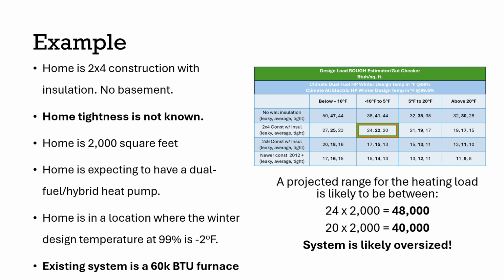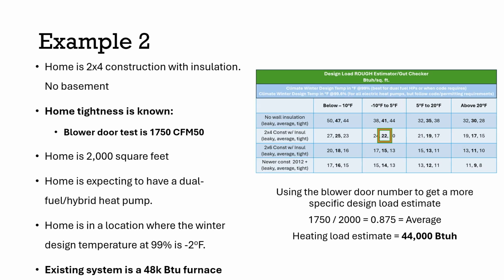So if I'm that technician out on that no heat, no cool call, and I'm about to call the boss, and I'm about to say, I think we need a salesperson to come out, you can say, I think this one is a full ton or more oversized, right? That's how this tool works.